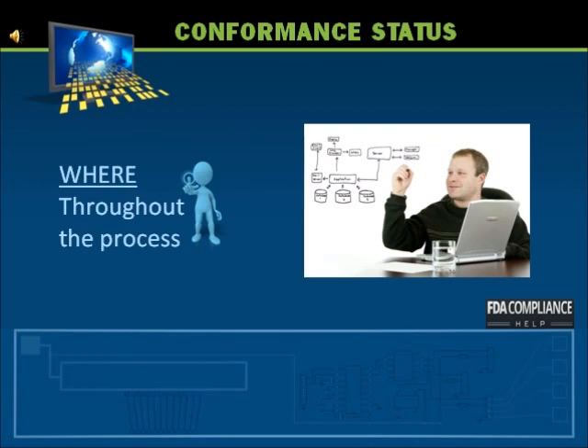The types of facilities responsible for meeting these requirements shall also identify, by suitable means, the acceptance status of product to indicate the conformance or non-conformance of these items. The identification of acceptance status shall be maintained during manufacturing, packaging, labeling, sterilization, installation, and servicing of the product to ensure that only those which have passed the required acceptance activities are distributed, used, or installed. See Section 820.86 of the QSR for details.